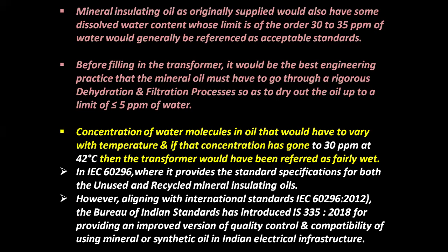IEC 60296 provides the standard specifications for both unused and recycled mineral insulating oils. However, aligning with international standard IEC 60296 2012, the Bureau of Indian Standards has introduced IS 335 2018 for providing an improved version of quality control and compatibility of using mineral or synthetic oil in Indian electrical infrastructure.